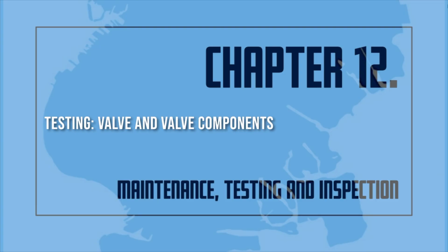High priming water levels can affect the operation of supervisory air or nitrogen pressure maintenance devices. Testing the water level is done by opening the priming level test valve. If water flows, drain it. Close the valve when water stops flowing and air discharges. If air discharges when the valve is opened, the priming water level could be too low. To add priming water, refer to the manufacturer's instructions.